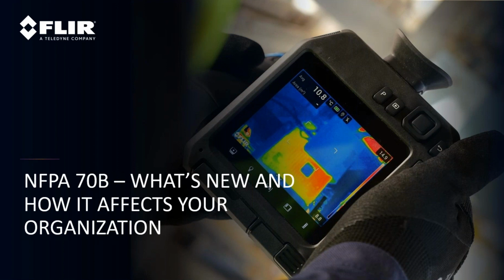Maybe yours specifically, but really anywhere where we have electrical equipment. The best way to quantify this: if you have some form of a transformer in your facility, basically you are in a position where 70B starts coming into place. So 70B is not for homeowners. It's not for smaller buildings where there is not a transformer stepping down power. It's really more in the commercial, industrial, institutional type spaces where you have larger electrical equipment through a larger distribution setup in the organization. So I do get that question from time to time. Figured I'd start off by answering it before we get into it.